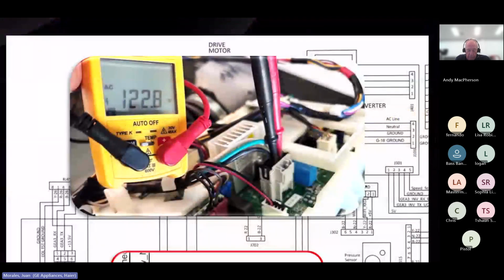This is what a lot of technicians miss. They don't check it, either because nobody trained them or they just don't bother. They say, I replaced the inverter, replaced the motor, still no spinning, try your main — at that point you're just swapping out parts. But if you diagnosed it initially, you'd know it was your main all along. Very, very important that we understand this concept. Any questions about this part before I move to the other thing that could cause this not to spin?